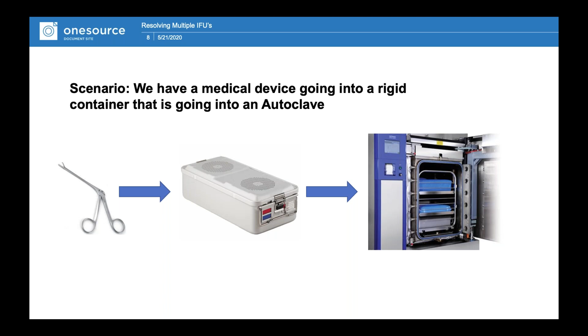This happened to be a 733 model of a sterilizer, and I'll show you the IFU on the next slide. We're not there yet, but this is the Cliff Notes of the IFU: you can put 16 20-pound trays into the sterilizer. I put this up there. Who has 16-pound trays? If the FDA tells us we can be at 25 pounds with a container, trust me, those things are 24.99 pounds each.